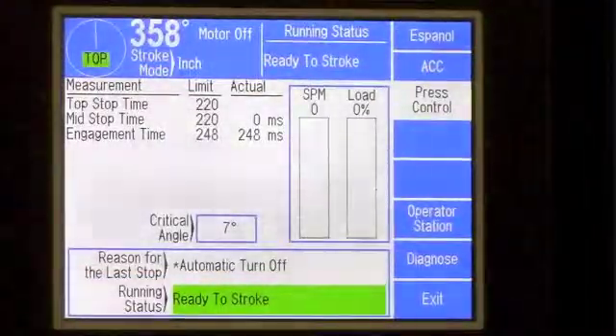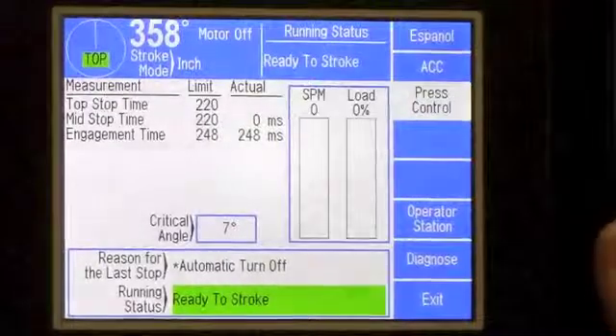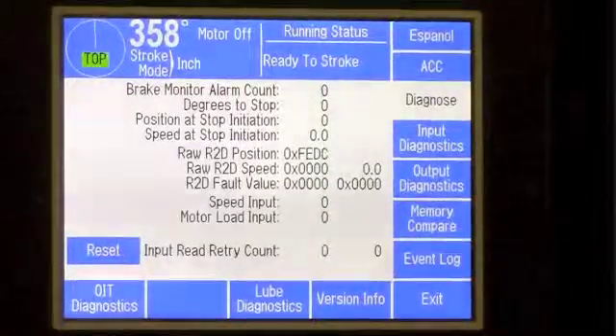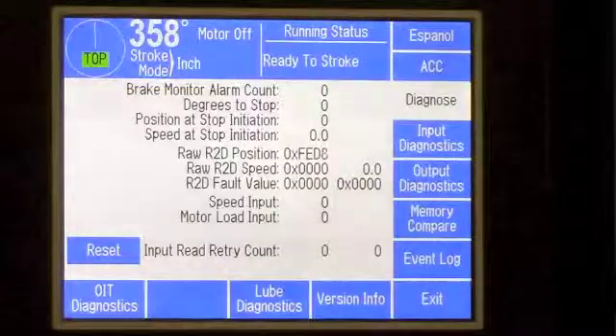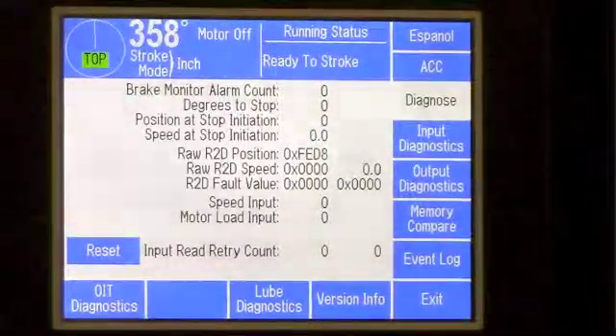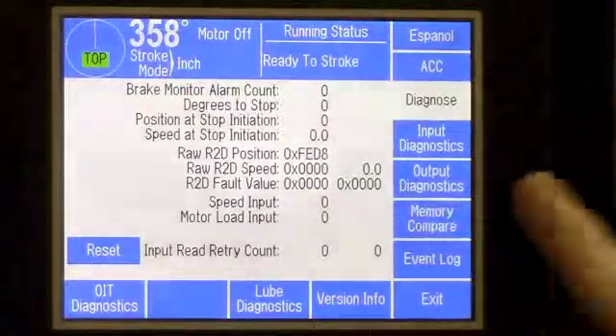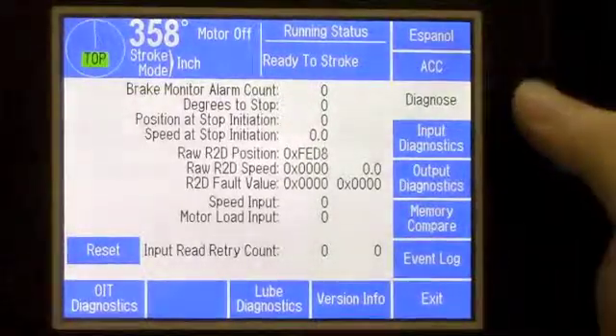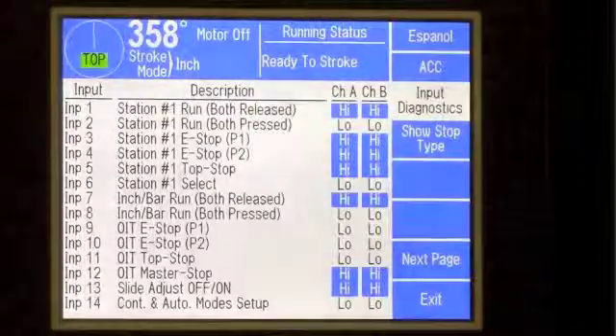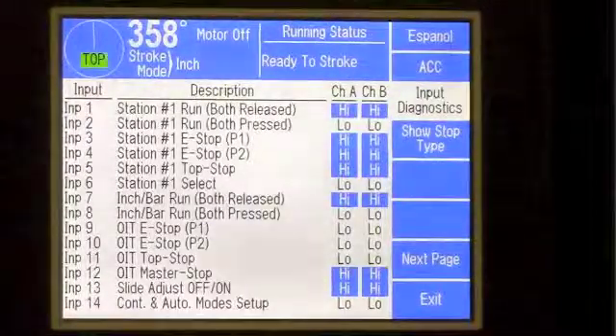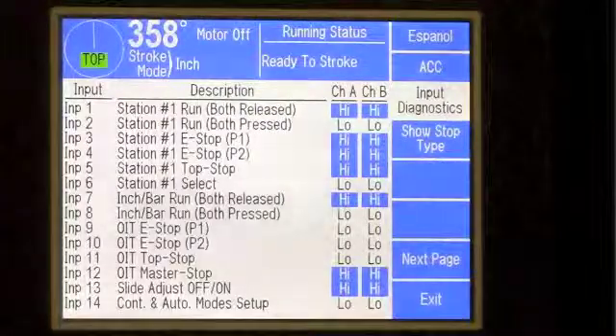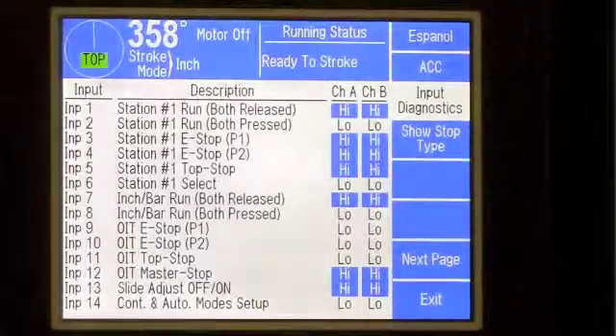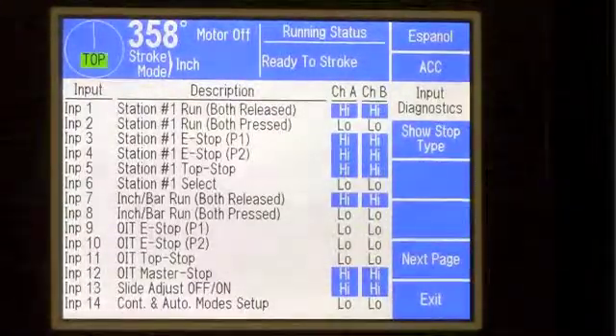From the press control menu, we now want to go into the diagnostics menu. Using the keypad on the right hand side, press 'Diagnose' and now we have our diagnose menu. There is several communication information going on internally in the link control, along with several menu choices for various diagnostics menus. In this case, we want to go to the input diagnostics. This shows the state of every component tied into the press control, whether it be a palm button, a limit switch, a pressure switch — any kind of function or device tied into the press control. This will show the state of each of those devices.